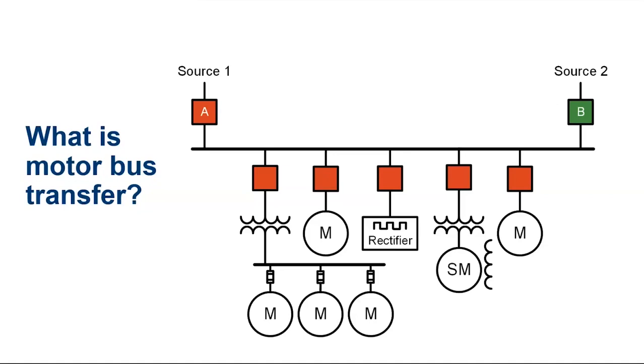A successful motor bus transfer can save a company millions of dollars each time it saves the plant from unplanned shutdowns. Motor bus transfer as a process is essential when you realize the operation of the process itself is more valuable than the individual pieces of the process. For example, a 10,000 horsepower compressor motor might be worth $2 million, but the loss of the entire process will cost $30 million and maybe up to 30 days of downtime.